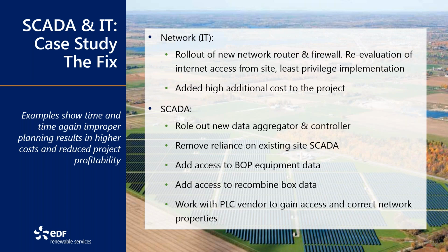From the SCADA standpoint, we rolled out a new data aggregator controller, again adding costs to the project to rip and replace systems that had been neglected. We removed reliance on the existing site SCADA, touching on that ISP issue, since we weren't able to remote desktop into the site SCADA consistently. So we had to switch the way we were getting that data and how we were integrating it.